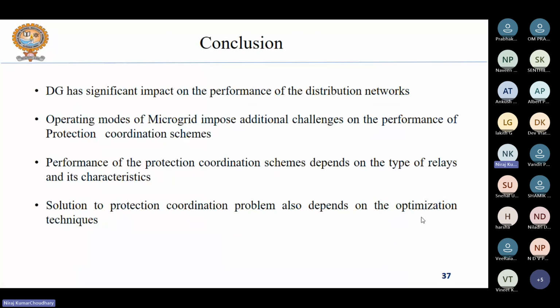So now I would like to conclude this talk, as we have seen that DG has a significant impact on the performance of the distribution network. Then we have discussed that the operating modes of microgrid have several challenges and consequences on the performance of the protection coordination schemes. Then the type of relay and selection of the relay along with the characteristics also impose several challenges on the performance. That's why you need to calculate the common optimal settings of the relay considering the grid connected mode and islanded mode capability, right? As well as the optimal combination of different type of relay characteristics, right?